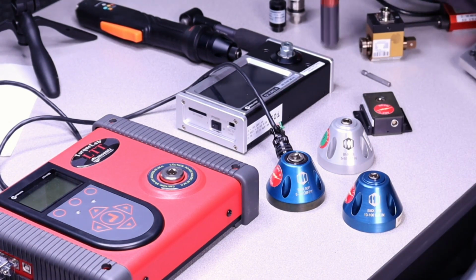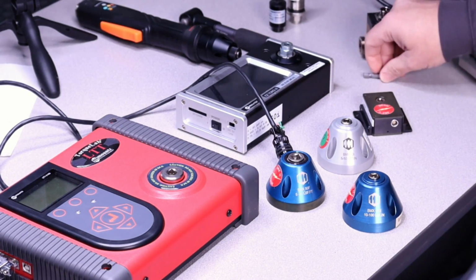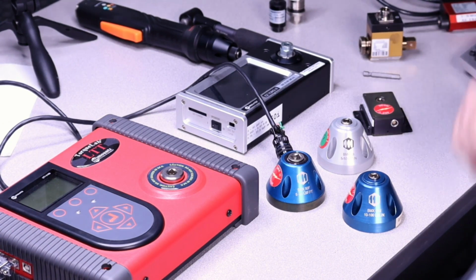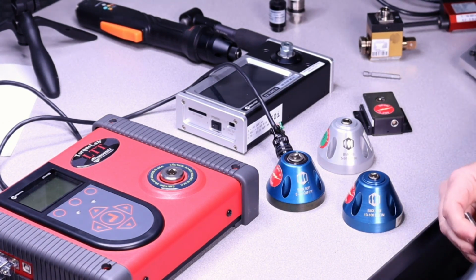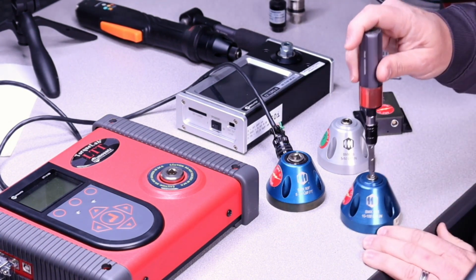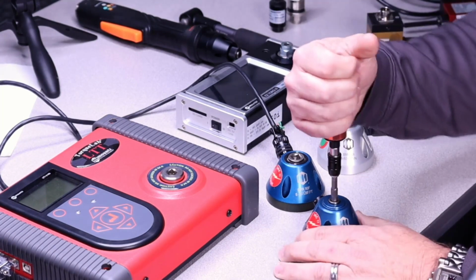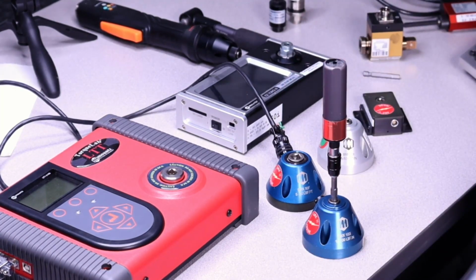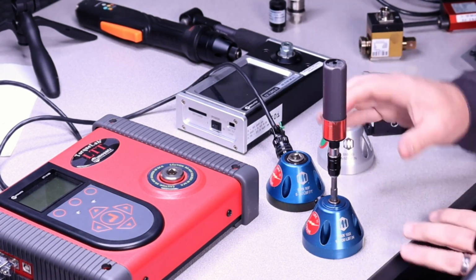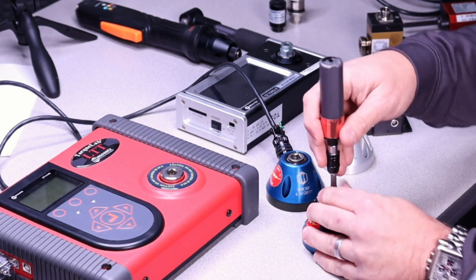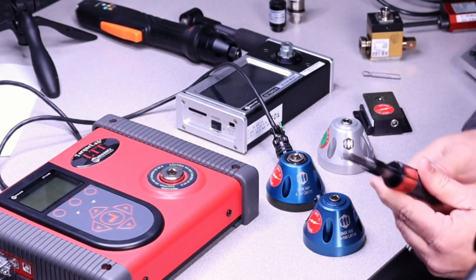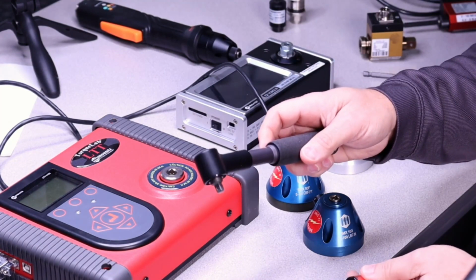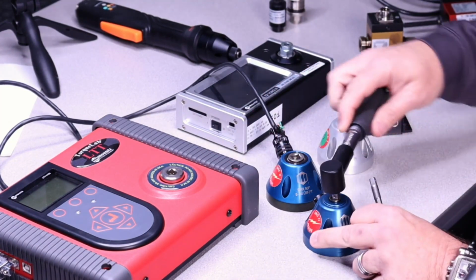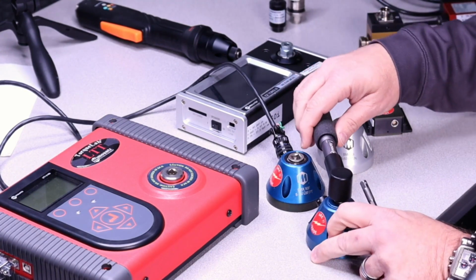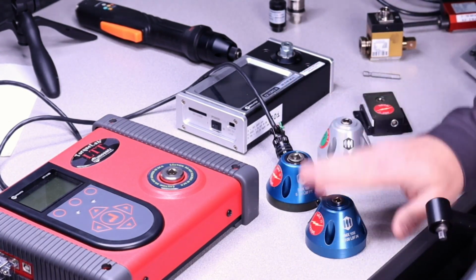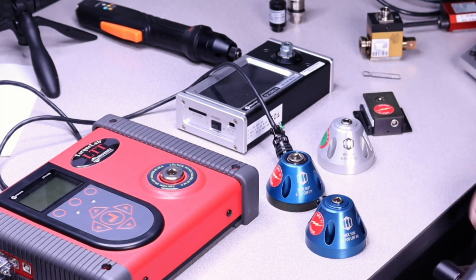To give you an idea of what this looks like, we can put our tool into the square drive and torque it, and it will give us the torque output of the tool. We can use these sensors with hand tools like this preset torque screwdriver, and we can also use them with torque wrenches. Same scenario: we put the tool into the drive, cam it, and that gives us our torque reading on the analyzer.